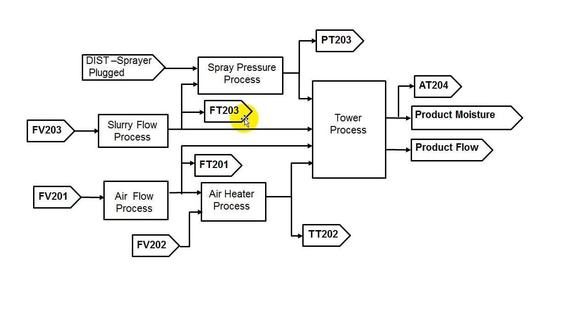The outputs of the controller become inputs to our process simulation, as those shown on the left-hand side. Also, we can introduce disturbances into a process that can be used in operator training and also in checking out our control system. The outputs of our process then become the inputs of our control. So those are being written to the input blocks that are normally used to access the transmitters in the plant. So from the control system standpoint, by connecting the simulation into the control, it looks as though you're operating in the plant environment. So it can be very effective in terms of control checkout.